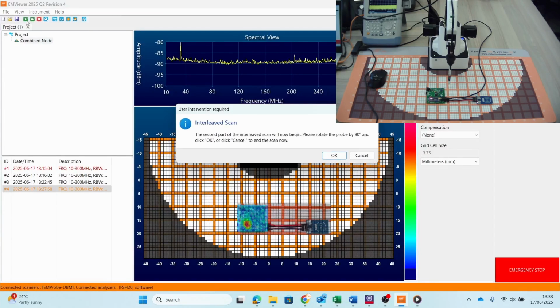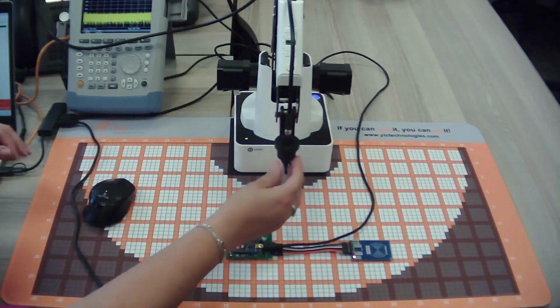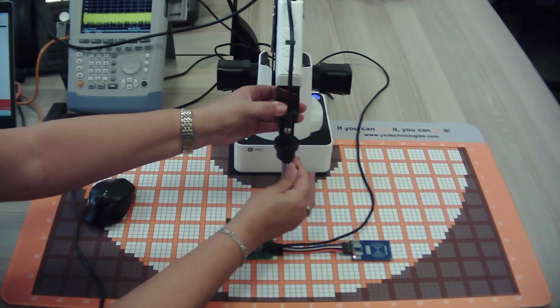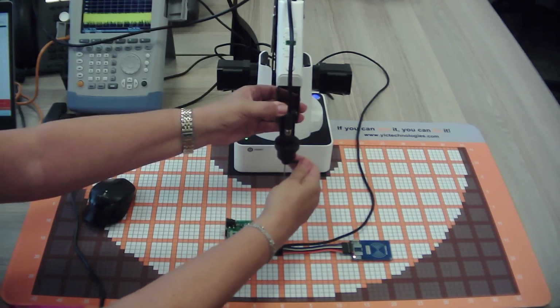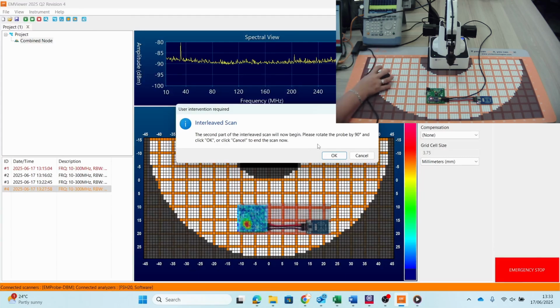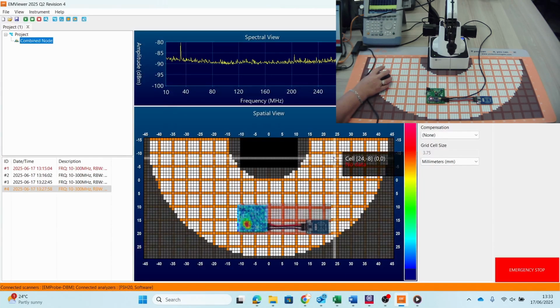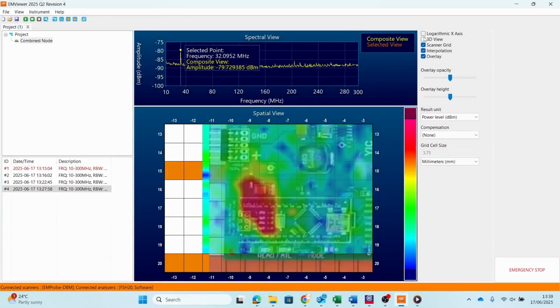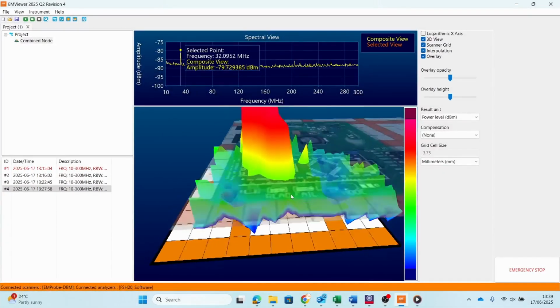Once the first half of the scan is complete, follow the instruction on screen and rotate the probe 90 degrees. Push the probe up gently and move into position. You will hear the click when the probe is in place. Click OK, and the second half of the scan will start. A level 2 scan is much clearer than a level 1 scan in most scenarios.